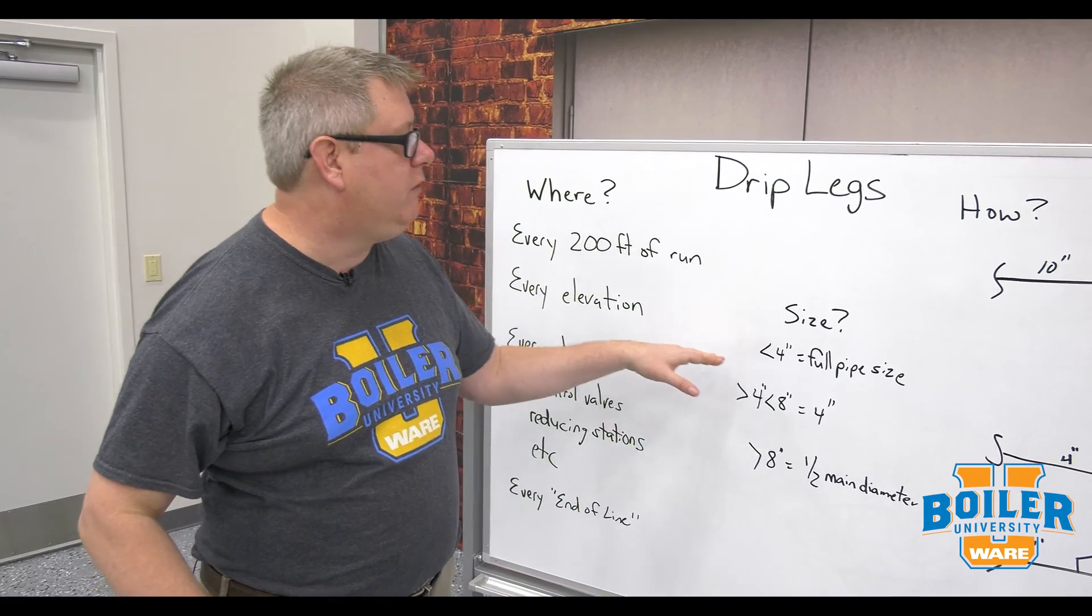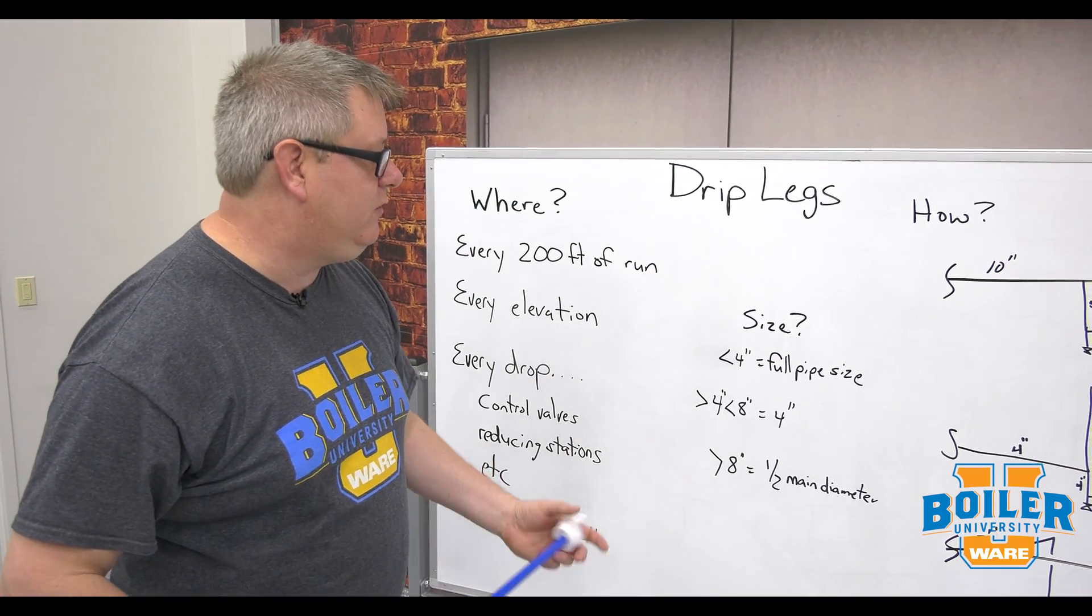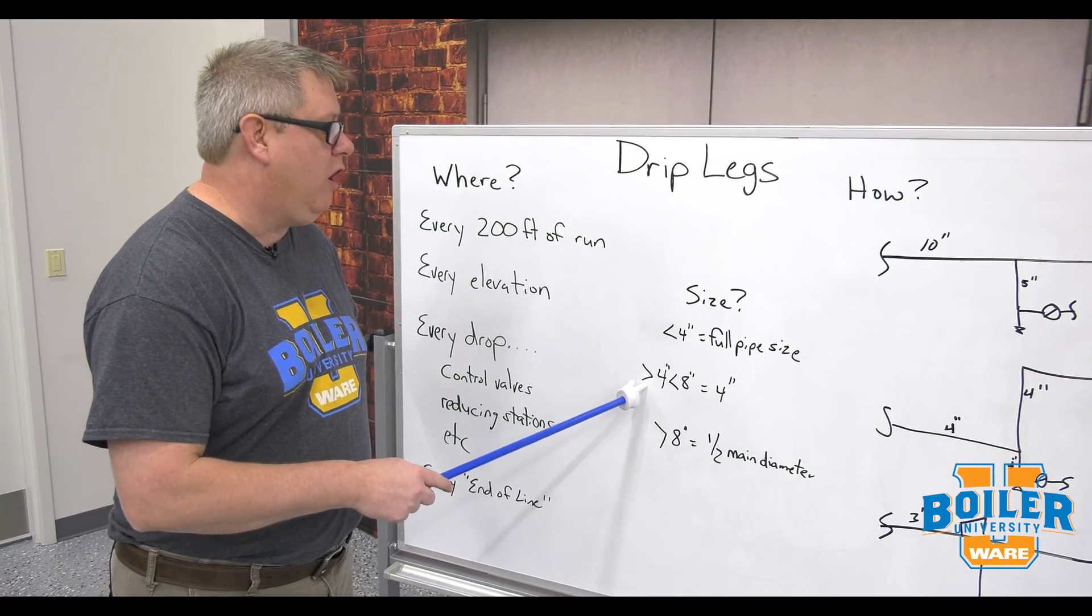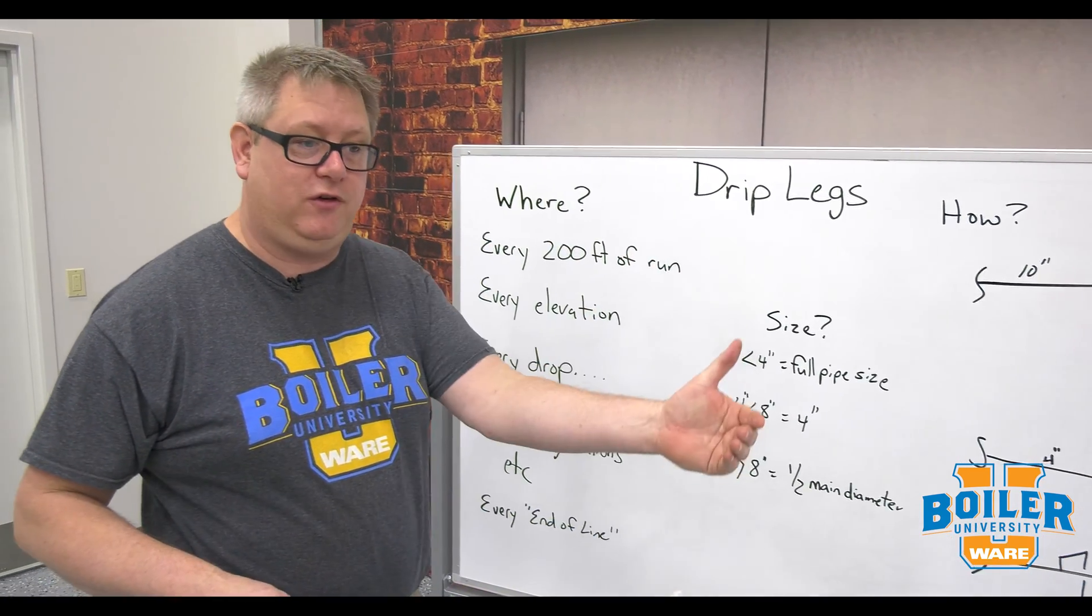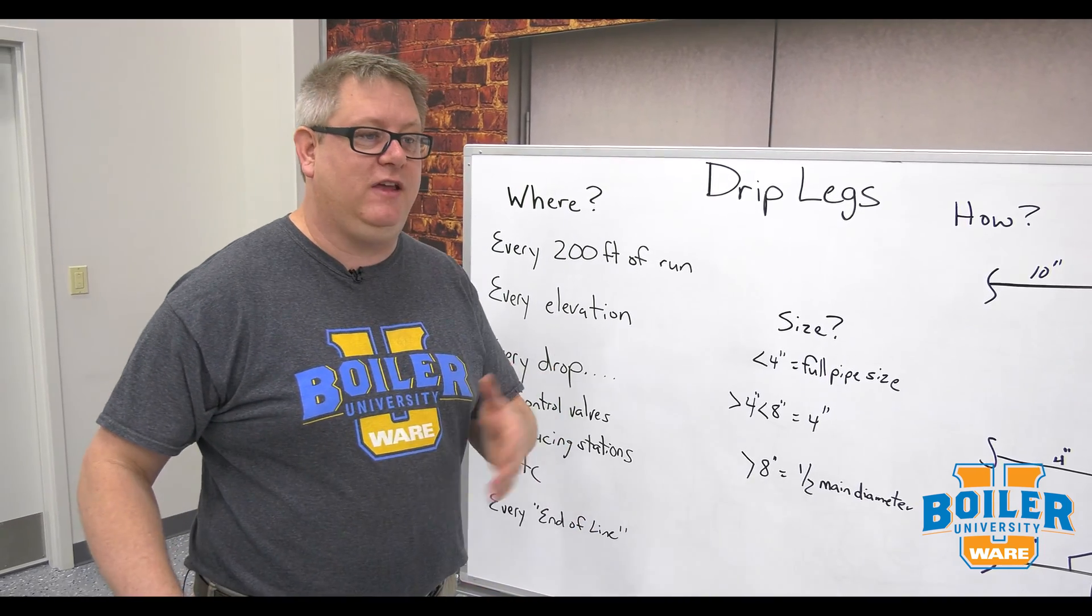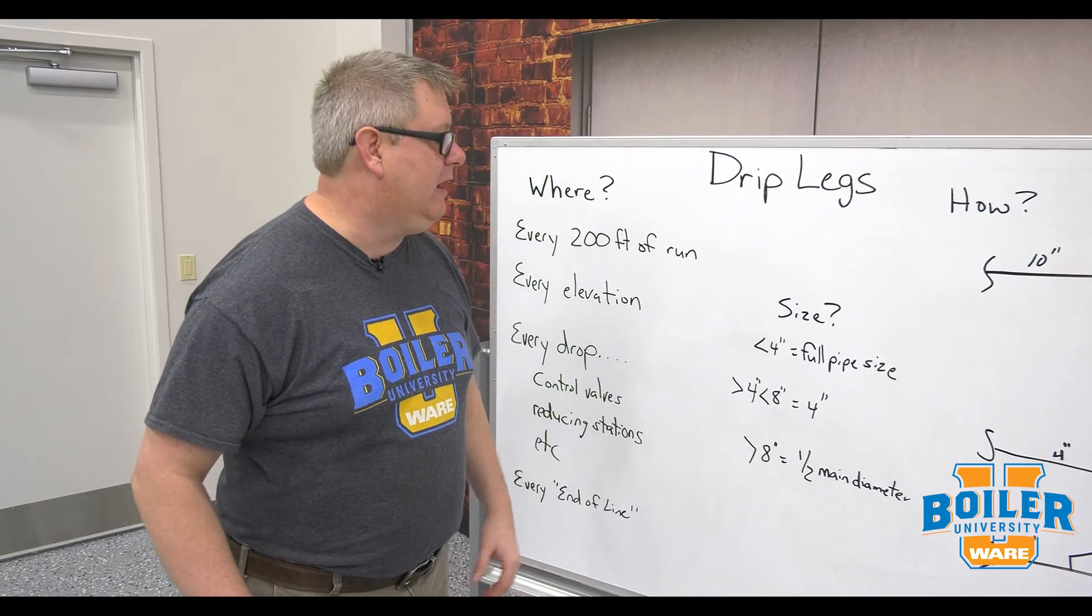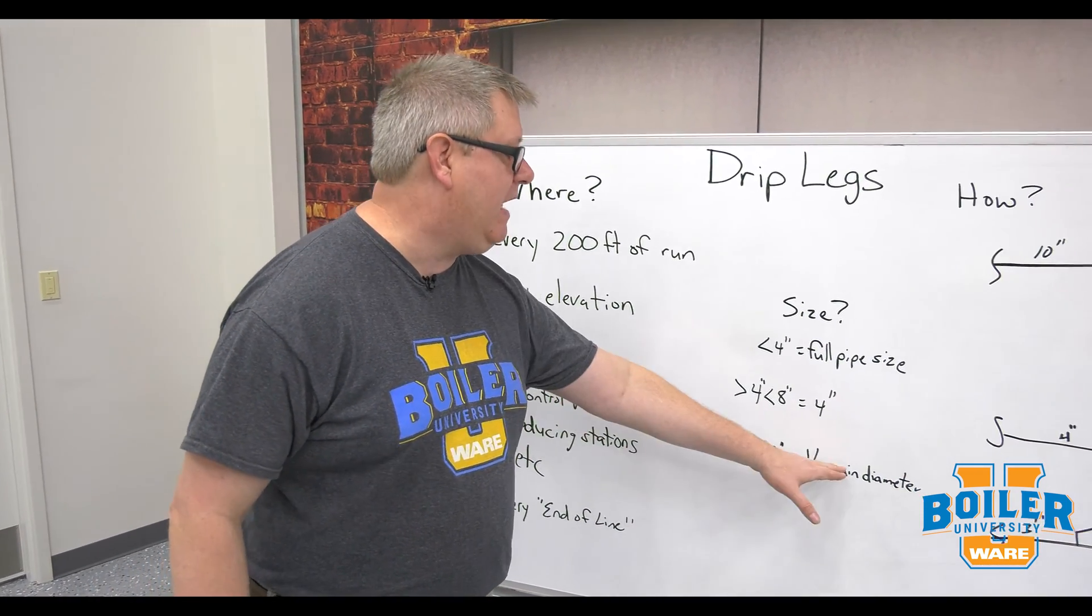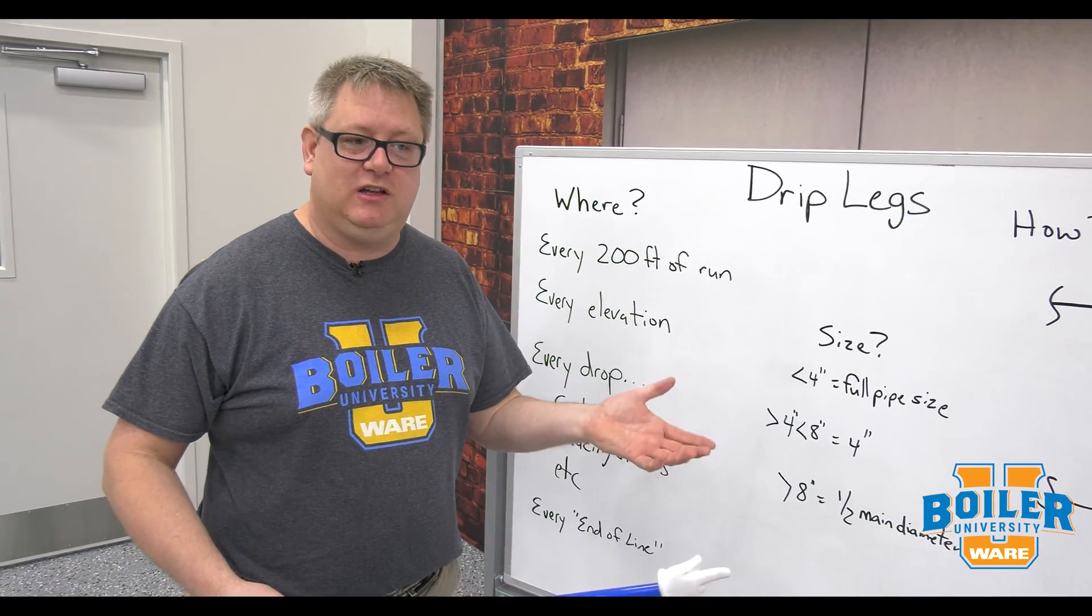So we use a full-size T to drop down and a full-size diameter drop for collection of the condensate. If we're larger than a 4-inch main, we're going to use 4-inch for our drip leg up to 8-inch pipe. So basically that's half until we get to 8 inch. Above an 8-inch main, we're going to use half of the main diameter. So if we have a 12-inch main, a 6-inch drip leg; 8-inch main, 4-inch drip leg.